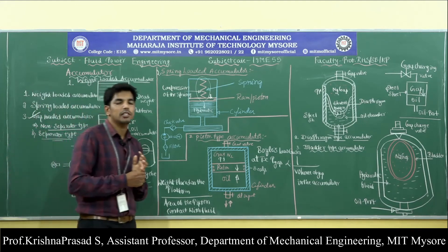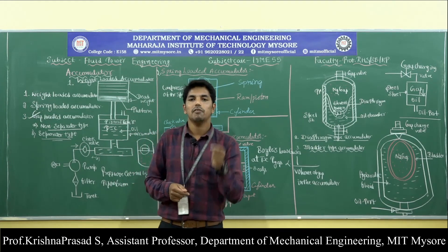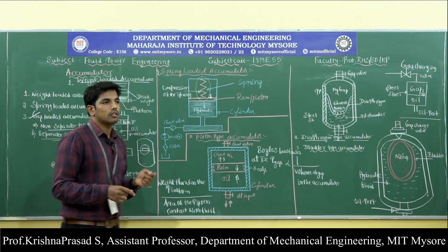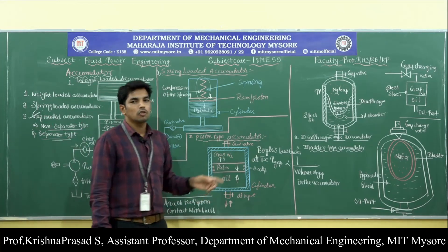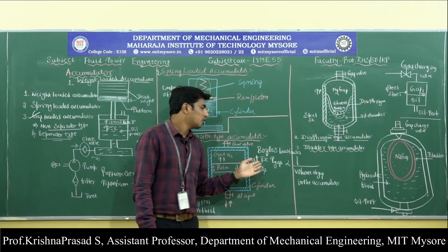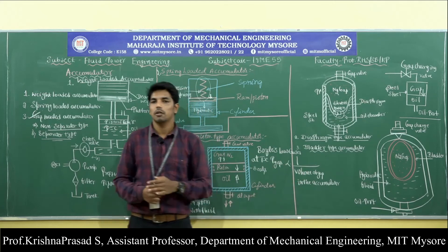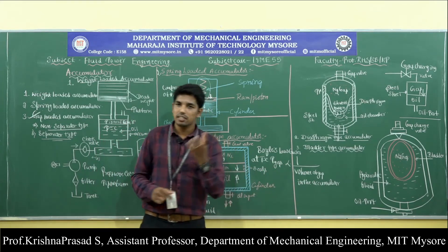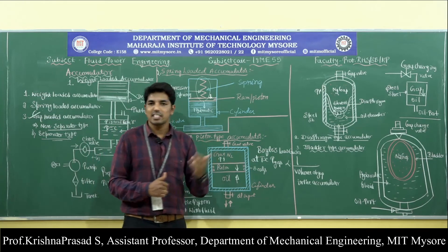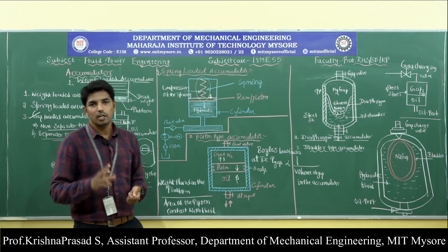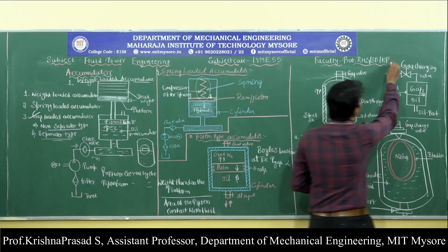In the gas loaded accumulator, force is exerted on the oil using compressed gases. It operates on the principle of Boyle's Law: at constant temperature, the pressure of gas is inversely proportional to its volume. For example, if the volume is cut in half, the pressure doubles. Gas loaded accumulators are of two types: non-separator type and separator type.